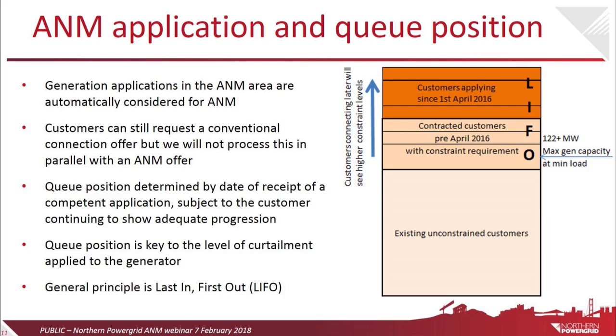Your queue position in the ANM scheme is currently determined by the date of a complete and competent application, and your queue position in and amongst all of the other ANM customers will influence the likely level of curtailment. The order in which generators will be curtailed for network constraints is based for this scheme on the last in, first out principle, which means that the last person in the queue will be the first person to be curtailed for any relevant constraint. And conversely, the customer at queue position number 1, the first person to apply with a competent application, will suffer the least curtailment of the ANM customers.